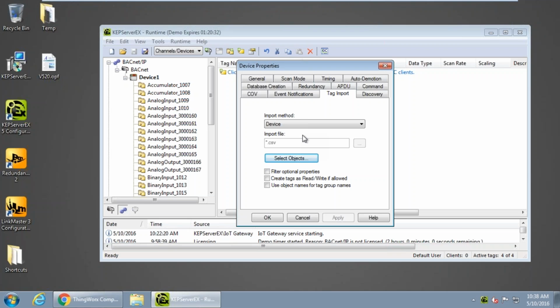So it might be interesting, this type of thing, for those of you not using it, building control information, especially if your process is sensitive to the environment of the building, to humidity, to temperature, and so forth, and you have a facility staff that's using BACnet controllers. You can actually bring this into your control systems or into those cloud-based systems to mash up that building data with process data to maybe get a more accurate view of how your environment is perhaps affecting your process. So tons of neat ways to leverage this data and to maybe form new partnerships if you do have a facilities group that is already using these BACnet objects and you're using Kepware. So just some background on that.